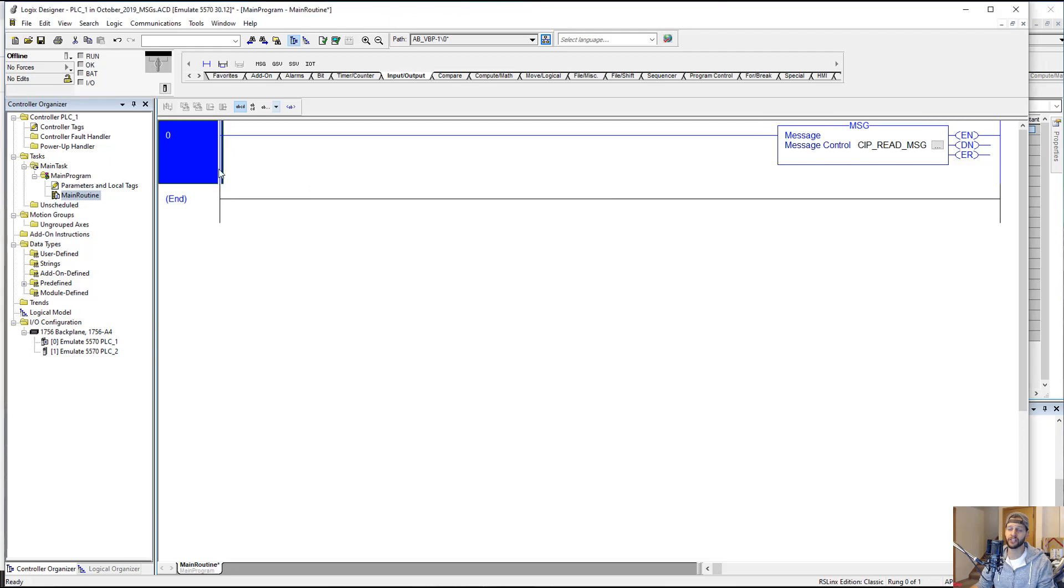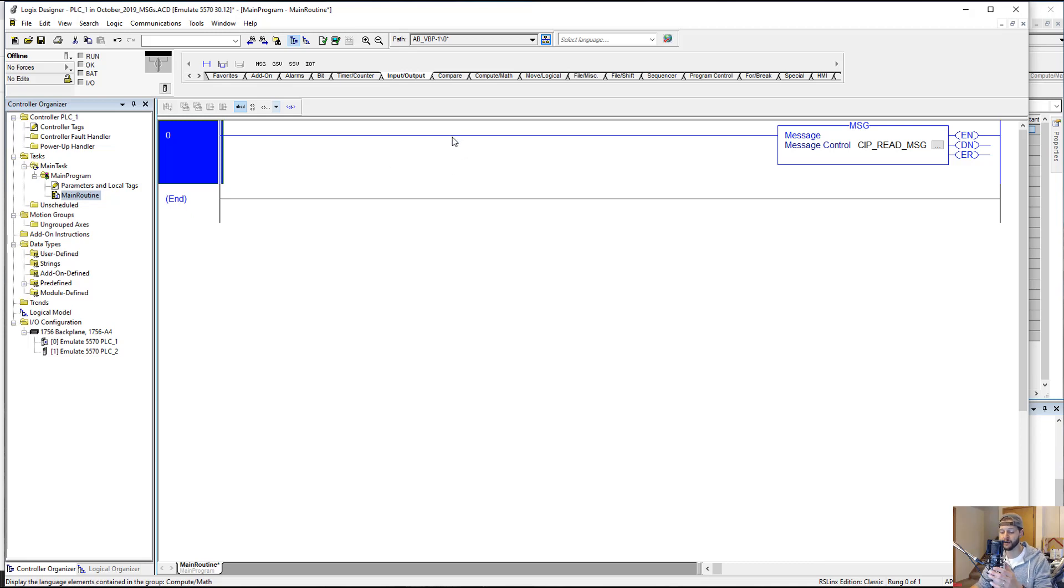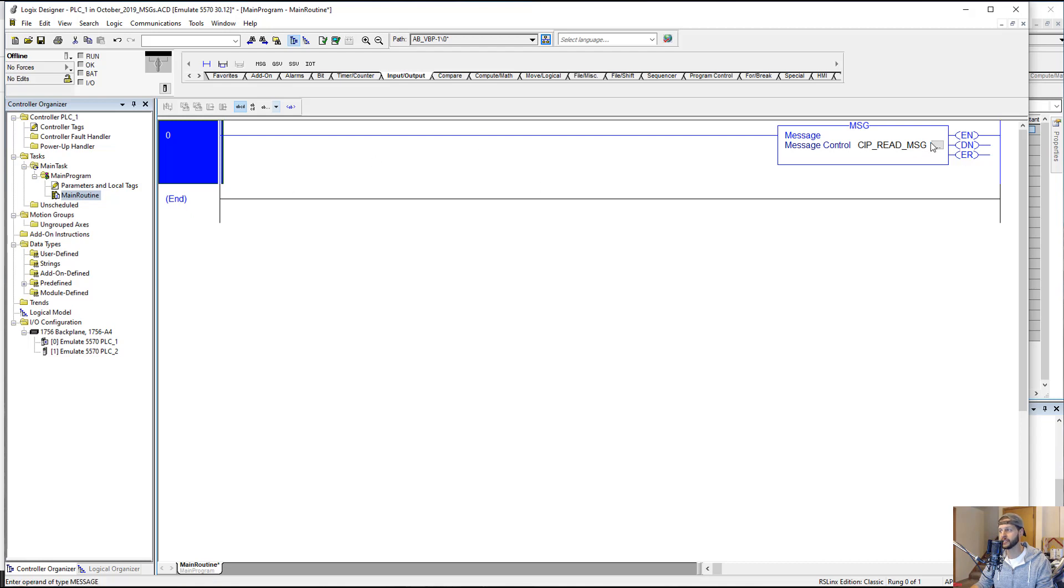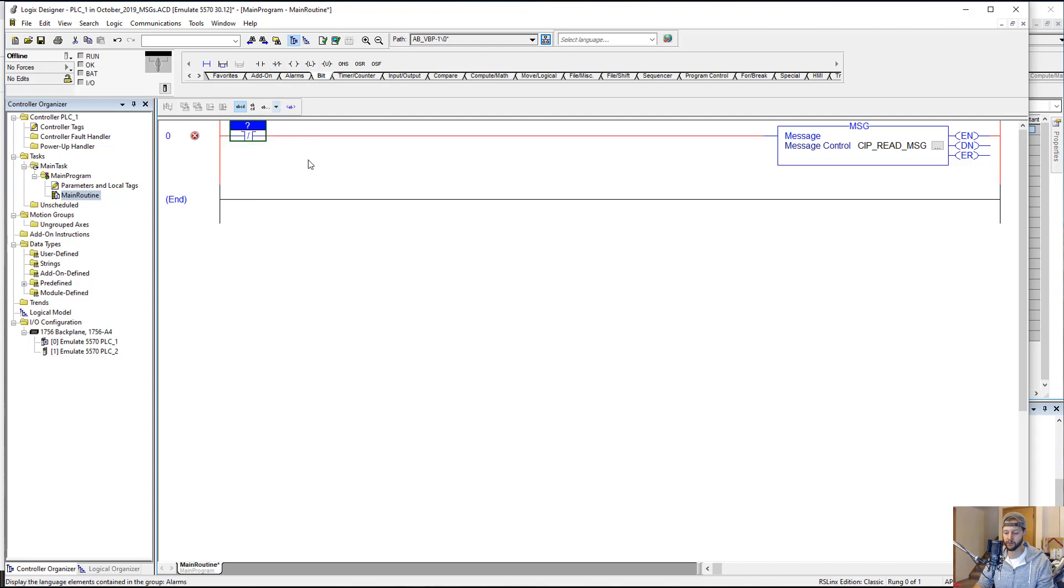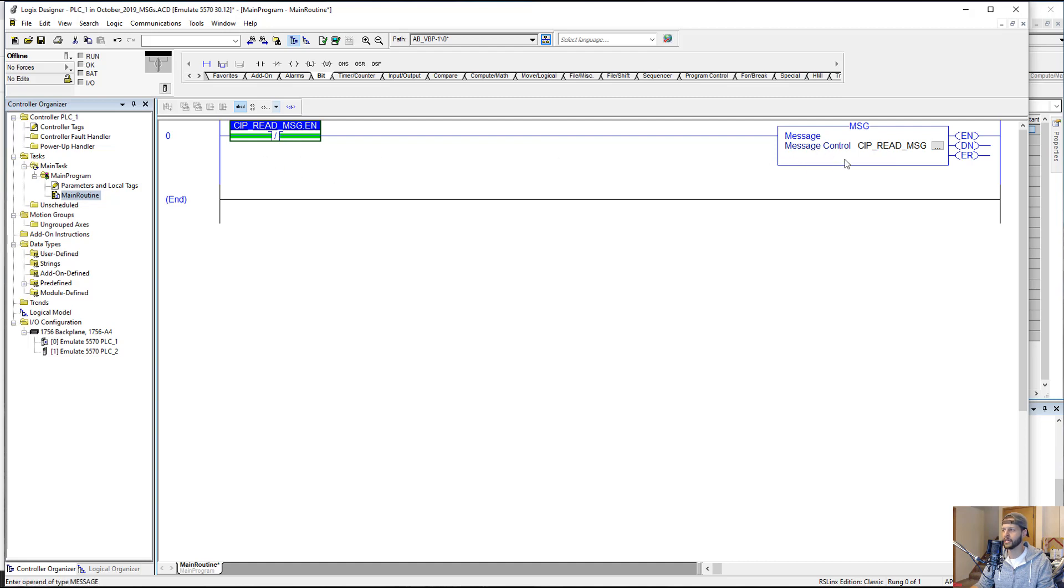One more thing before we test our message instruction. The way a message instruction works is that when the rung is true, the message instruction executes once. As soon as we put this in run mode, this instruction would execute once. We'd read the data once and then we'd be done. If the data in PLC2 changed after that, we wouldn't see it. What we want to do is set it up so that this rung keeps going from false to true, false to true, so that we can get this to continually execute. The easiest way to do that, and this works almost always unless you have a really big program and maybe some task timing issues that you need to deal with, all you have to do is do a CIP read message dot EN, which is the enable bit of this message instruction, and that will continually toggle the rung and continually execute that message instruction.